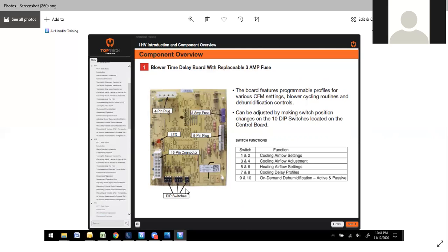And we'll go over the dip switches right here. You have the various dip switches. Switch 1 and 2, that's your cooling airflow settings. Switch 3 and 4, that's your cooling airflow adjustment. That lets you tweak that a little bit, fine tune that. 5 and 6 is your heating airflow selections. 7 and 8 is your cooling delay profiles. And then number 9 and 10 is your on-demand dehumidification, whether it's active or passive.